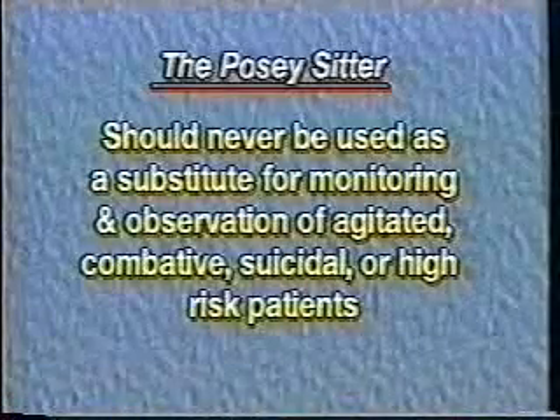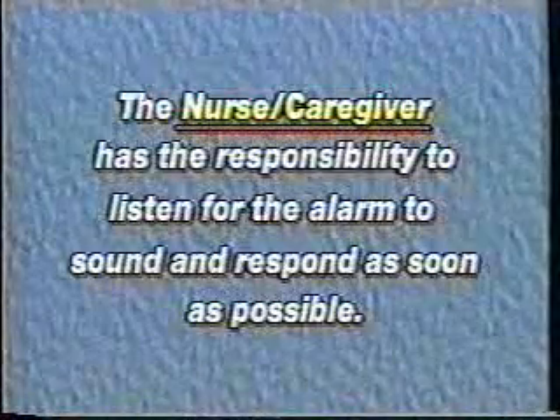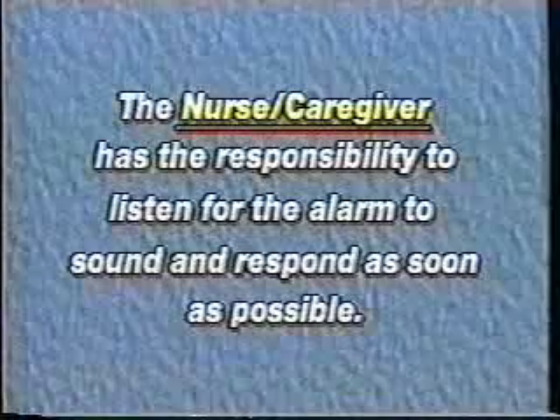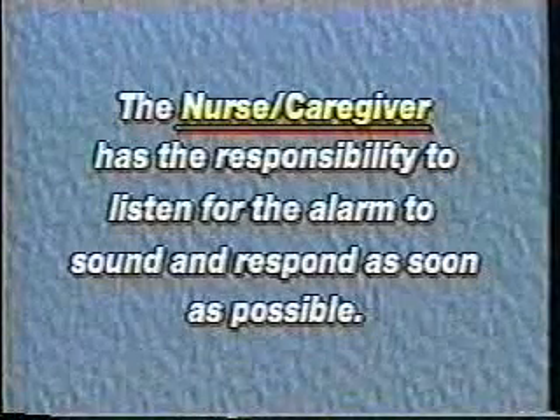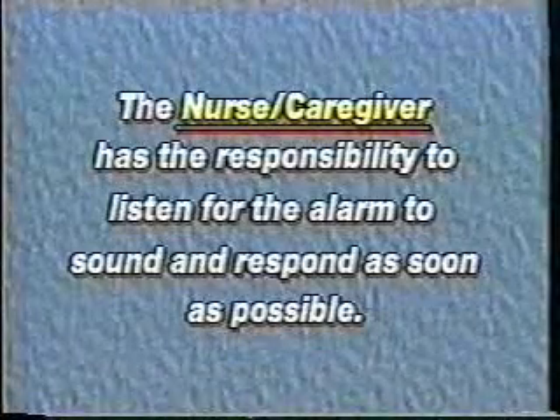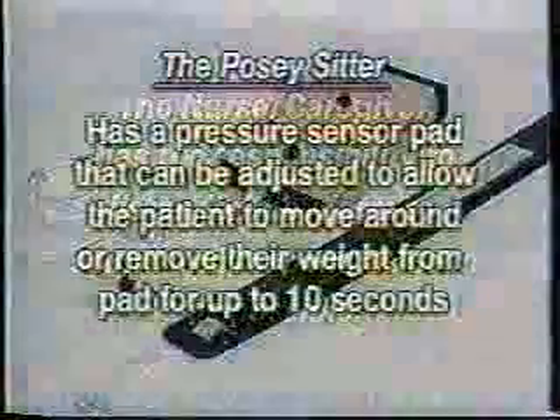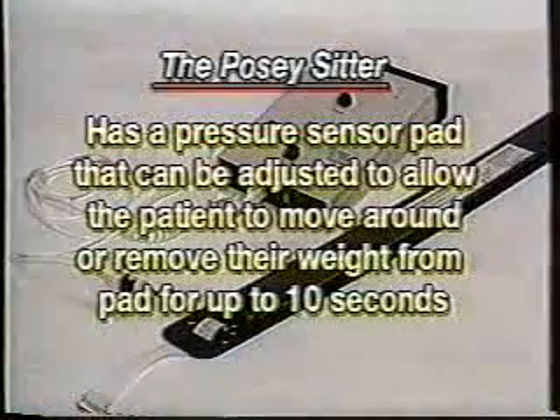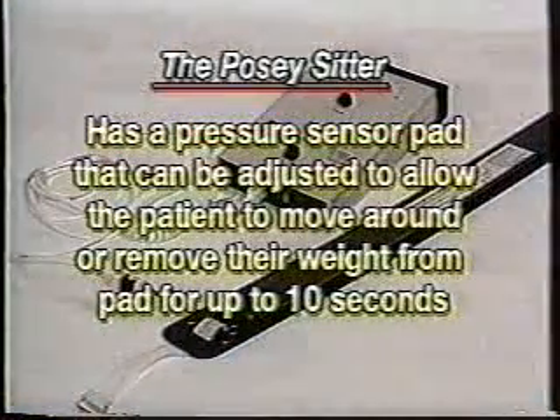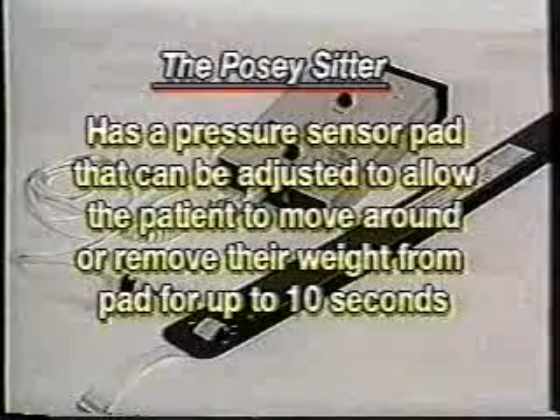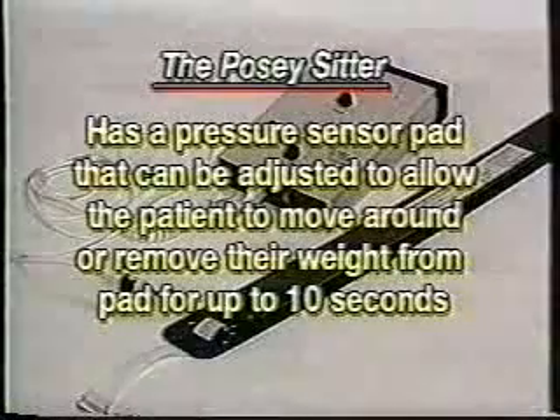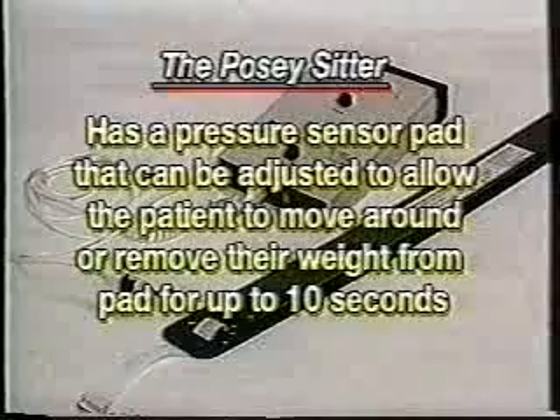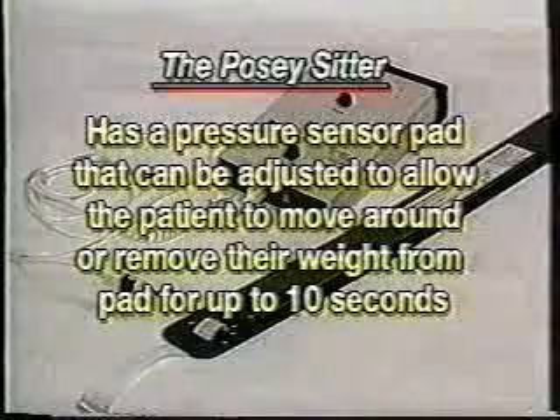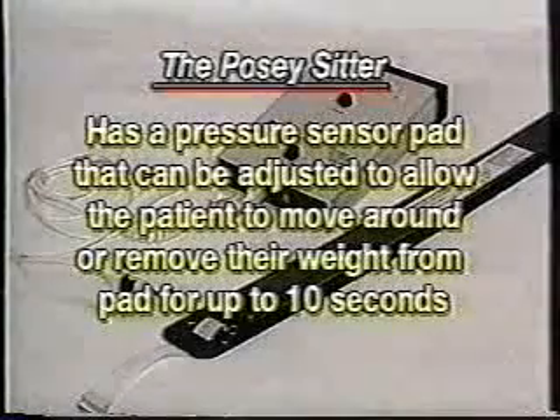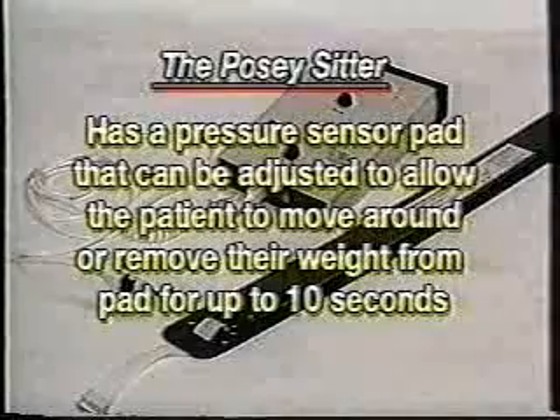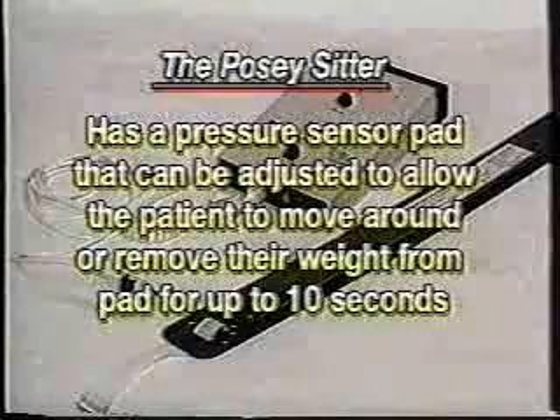High-risk fall patients. The caregiver has a responsibility to listen for the alarm and to respond as soon as possible to see what has caused the alarm to sound. The Posey sitter uses a pressure sensor pad that is attached to an alarm box that will sound an alarm when the patient moves their weight off the pad. The Posey sitter can be adjusted to allow the patient to move about in bed and remove their weight from the pad for periods up to 10 seconds.